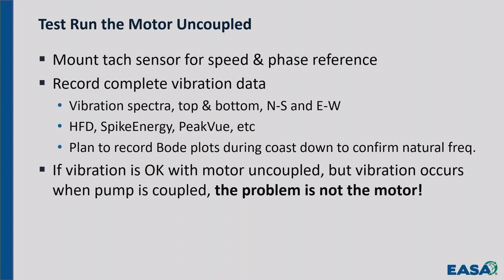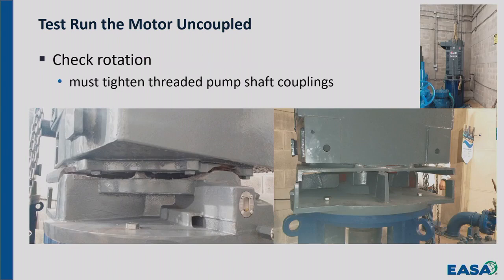Okay? All right. Do not start the motor coupled to the pump unless you know it's running the right direction. I can't think of any clearer lesson than to take a look at those pictures. Okay? That crack is not supposed to be there. The couplings are threaded. If you start it the wrong way, the couplings unthread and the shaft comes up, and this is what happens. Okay? This is why you always check the direction of rotation before coupling the pump.